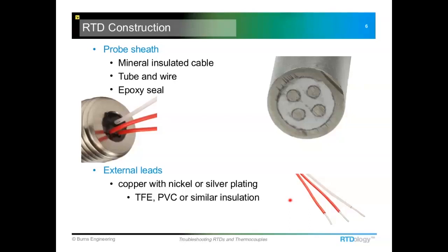The external leads or lead wires running down to the sensor in a tube and wire construction are typically copper, but they need either a nickel or silver plating to protect from corrosion at higher temperatures. Copper itself will handle maybe a couple hundred degrees Fahrenheit, and above that it starts to corrode and cause trouble. Nickel plating seems to be the most durable; silver works too but can tarnish and potentially cause trouble down the road.